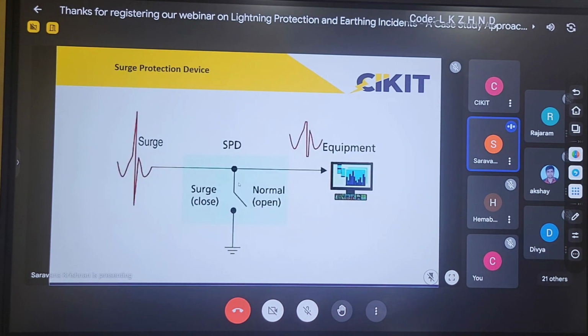Surge protection devices are nothing but fast acting switches. They normally act as an open switch at normal operating conditions. If any surge approaches and the voltage is above the threshold limit, the switch acts as a closed switch and diverts the surge to the ground. Once the surge magnitude returns to normal, the normal supply is resumed to the equipment. For that particular duration, the equipment won't receive any power supply because the energy is diverted to the ground, but we cannot feel the switching because it takes place for a microsecond duration. In simple terms, SPDs are fast acting switches which divert the surges to the ground.